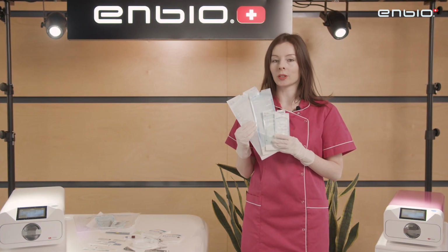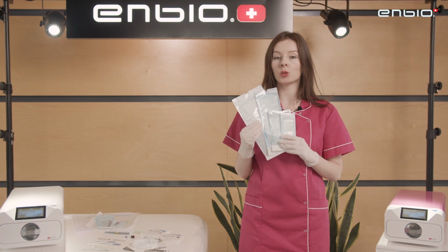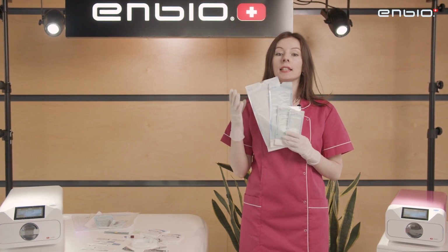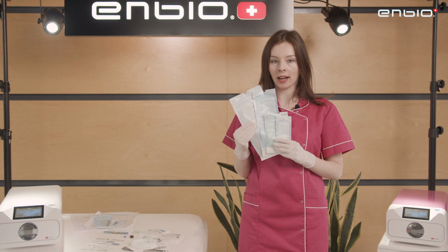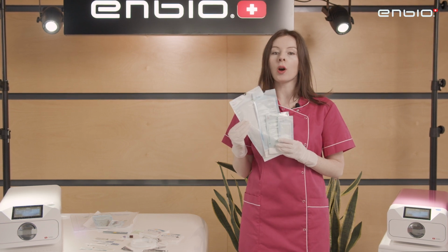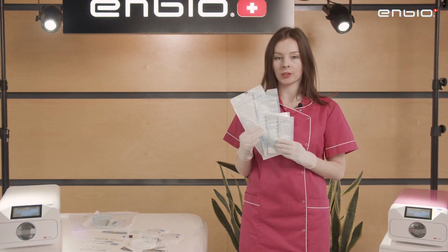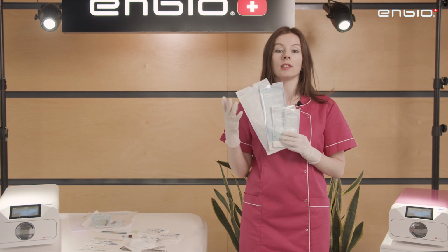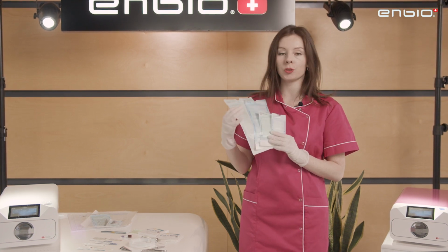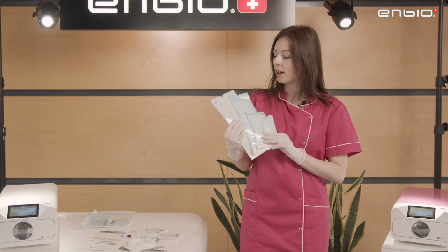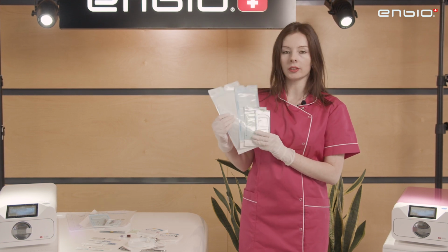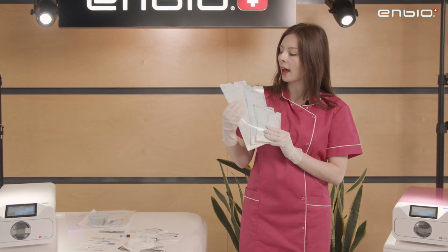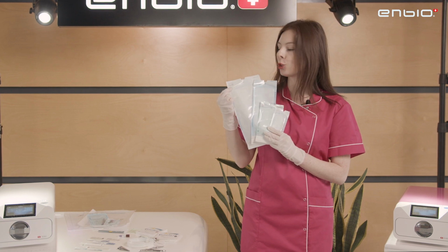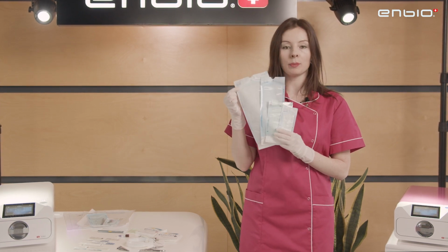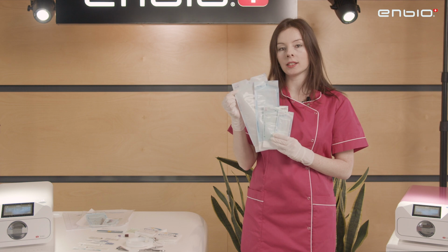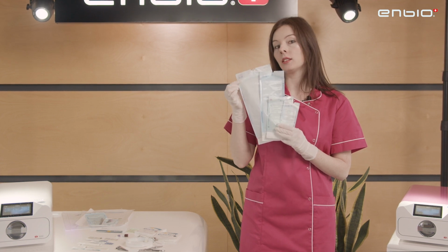When we select the sterilization pouches, it is important to take into consideration the technology of the sterilization device that we are using, and also the type of instruments that we are using, their size, and the number of tools that we want to introduce in one pouch. For instance, these sterilization pouches have an indicator here that show the fact that they are supposed to be used for sterilizers that use steam as the technology.